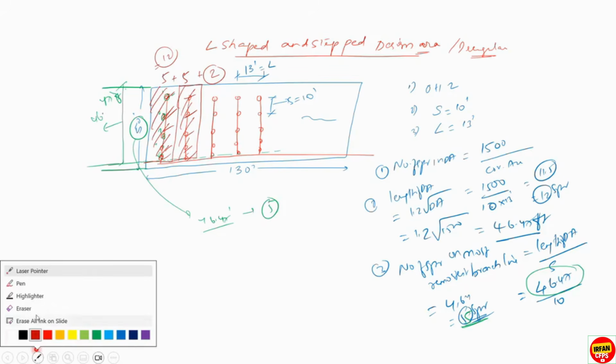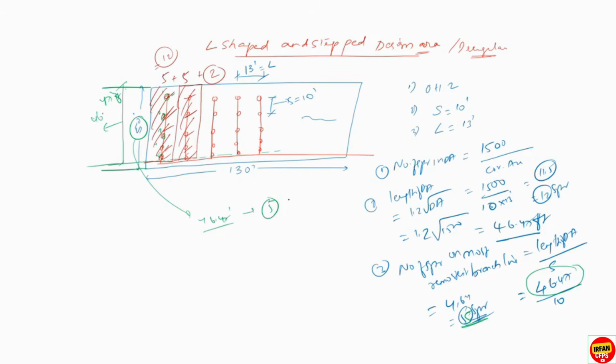Okay. So how can I say, because as I told you in the previous slide, for the design area you need to select the highest pressure demand and the highest flow demand. For highest pressure demand, you already get the highest pressure from the remotest area, the remotest point.